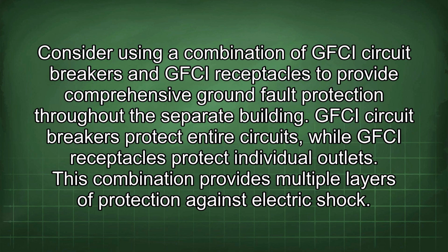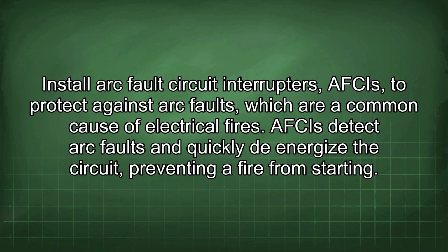Consider using a combination of GFCI circuit breakers and GFCI receptacles to provide comprehensive ground fault protection throughout the separate building. GFCI circuit breakers protect entire circuits, while GFCI receptacles protect individual outlets. This combination provides multiple layers of protection against electric shock. Install arc fault circuit interrupters, or AFCIs, to protect against arc faults, which are a common cause of electrical fires. An AFCI detects arc faults and quickly de-energizes the circuit, preventing a fire from starting.